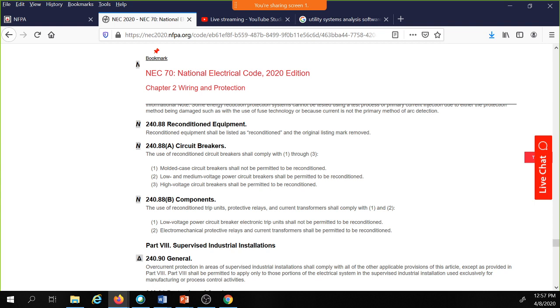All right, I'm just looking down through here. Even the code does not require listing equipment in general. I had one of our senior leaders ask me, hey, what section in the code requires circuit breakers to be listed? I had to break the news that circuit breakers aren't required to be listed—outside of 240.88, if you recondition it, now you're required to be listed. OSHA does not require all electrical equipment in the workplace to be listed. That's true. All right, so we've got some examples.